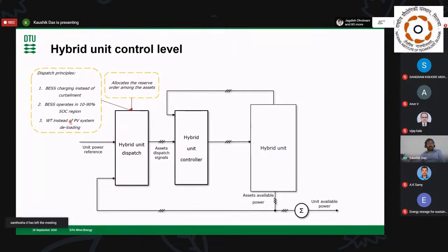So when you need to bring up the wind turbine, it takes more time, and things like that can also be taken into account. We chose that PV can be deloaded in that case since it's faster to bring back up. But wind turbine can also be deloaded if there's value in reducing the mechanical load on the wind turbine, which increases its lifetime.